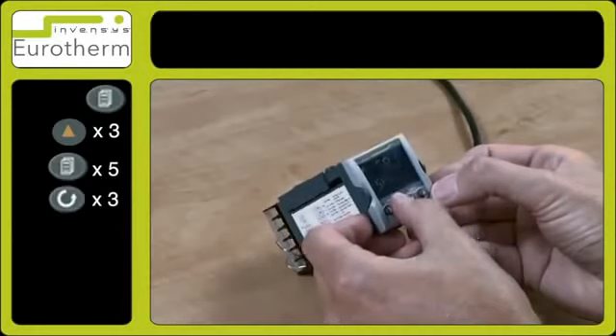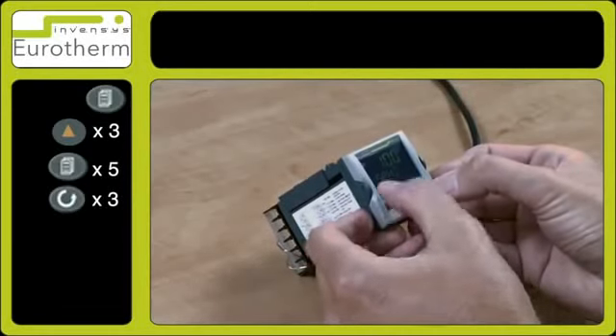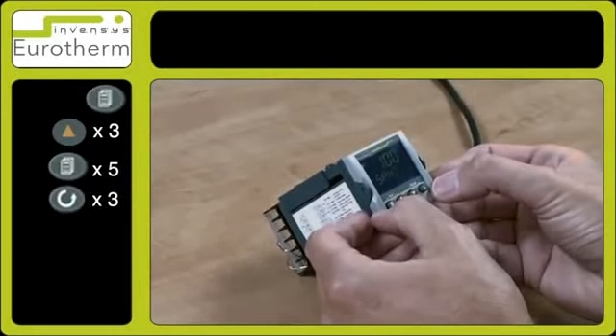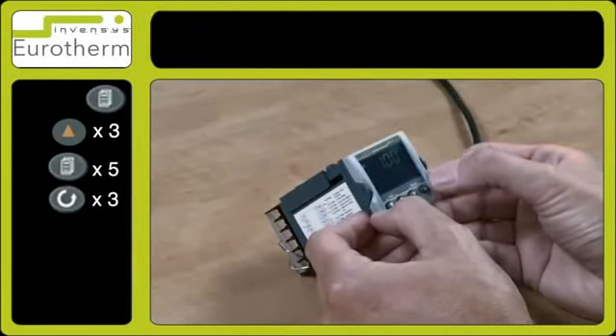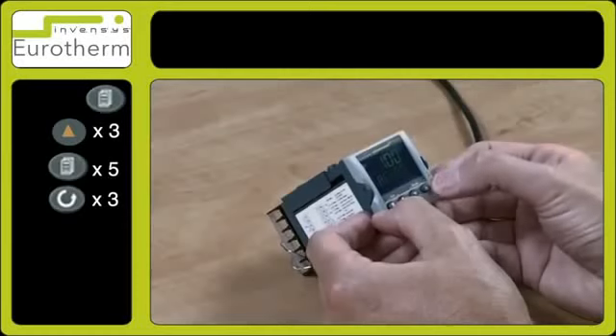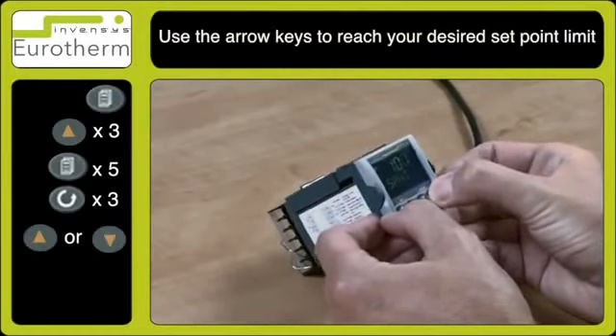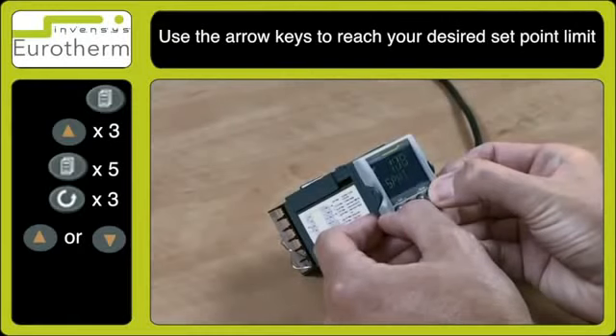Press the scroll key a few times until you see set sp.high, which is set point high limit, and you can see this is at 100.